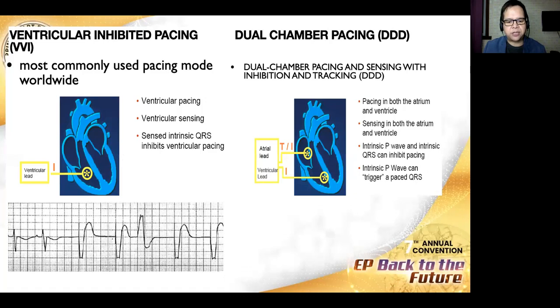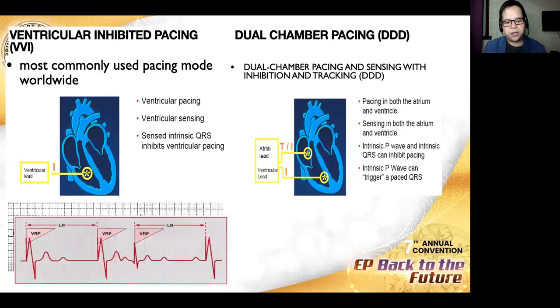And a sensed activity will inhibit pacing, as it should. Therefore, looking at the ECG, there is an intrinsic activity in the first 2 beats. Then after a set interval, the pacemaker senses bradycardia and delivers a pacing potential, followed by capture. Now, the 5th beat is an intrinsic PVC, which is sensed appropriately and thus resets the interval of the pacemaker, which will deliver a pace on the next cycle. So the basic interval is just the lower rate, or LR, below which the pacemaker will deliver a pacing potential.